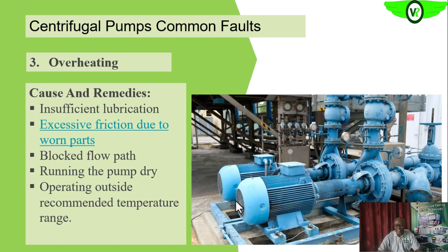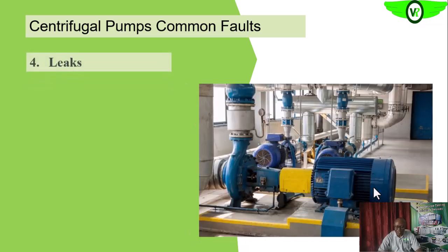If you operate the pump outside the recommended temperature range — for example, if the ambient temperature is 60°C when the equipment is designed for 40°C — the electric motor will first assume the ambient temperature, then heat from the windings during normal operation is added on top of that. This can take the motor temperature to a very high level, potentially burning out the windings. The pump components are also designed to operate within certain temperature ranges due to expansion and contraction considerations.